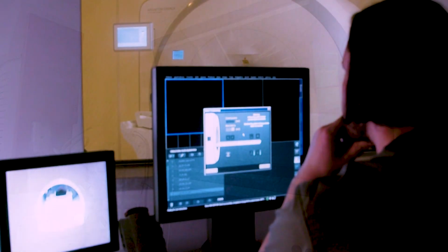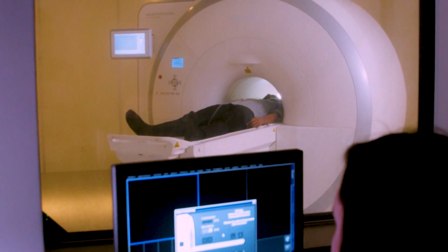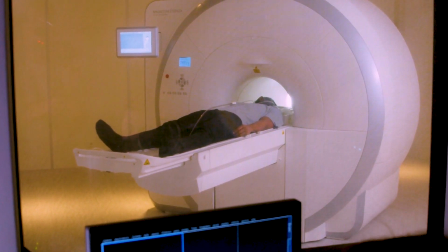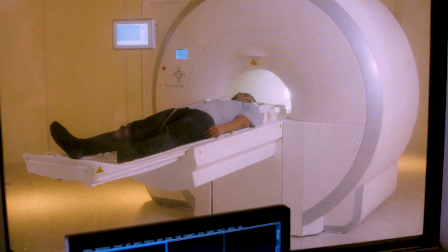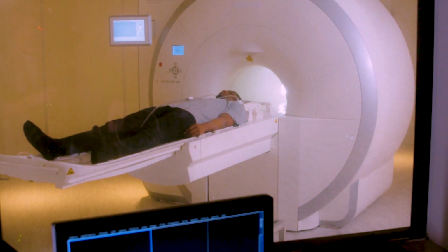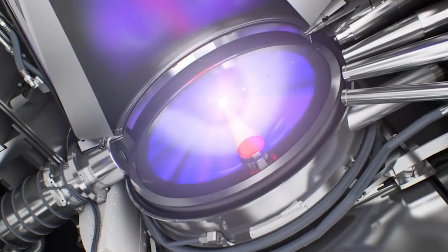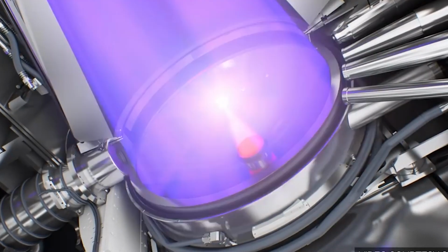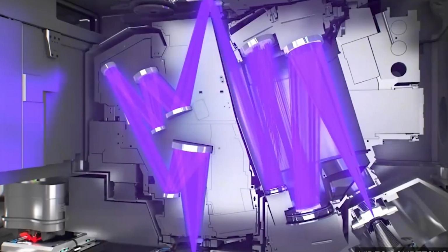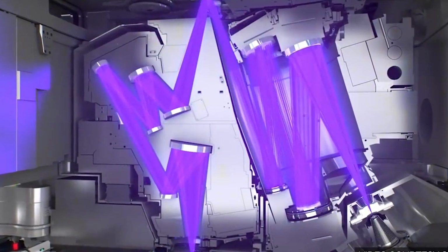In the case of magnetic resonance imaging machines, whether in hospitals or for test samples in laboratories, the situation is a little bit more complicated because the images are produced through a mathematical function, so there's not a linear relationship between vibration and distortion as there would be in the case of microscopes.